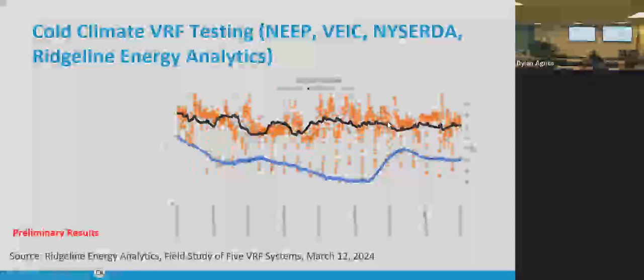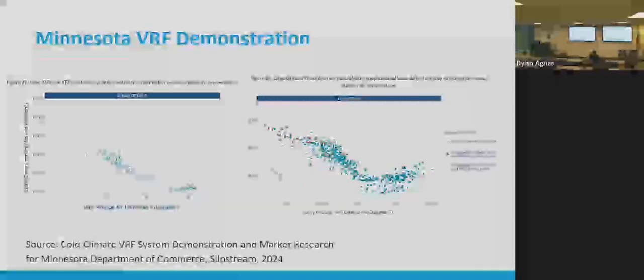It's pretty good performance. They had some mixed results. There were some real bummer ones that had been installed 10 years ago that weren't installed well, that performed with the COP under 2. So definitely a mixed bag, and installation matters, design matters a lot. But there were a lot like this, which even in very cold conditions performed well.